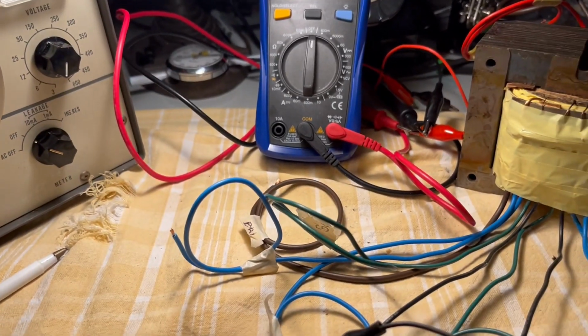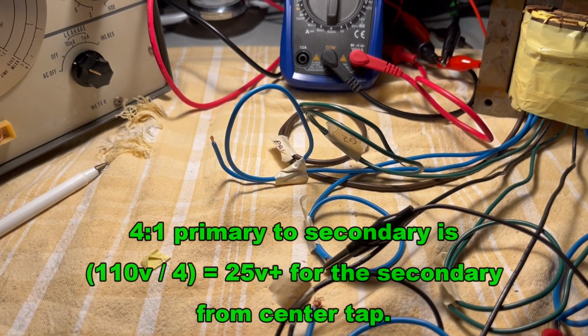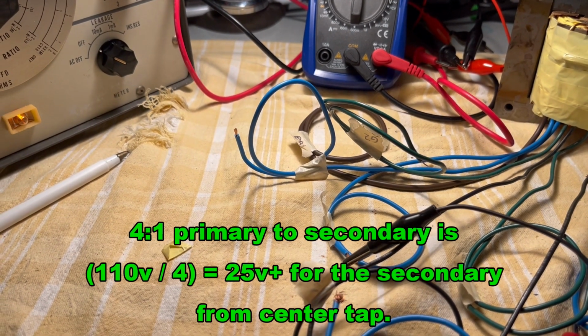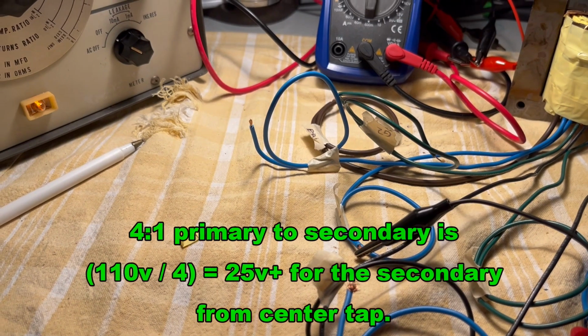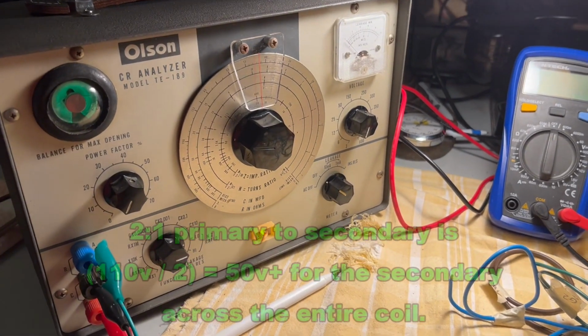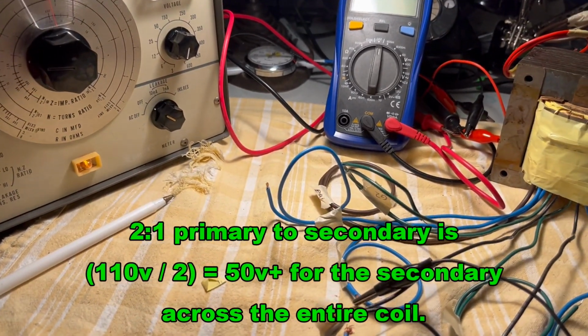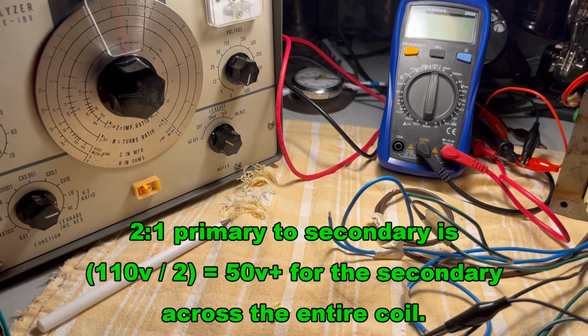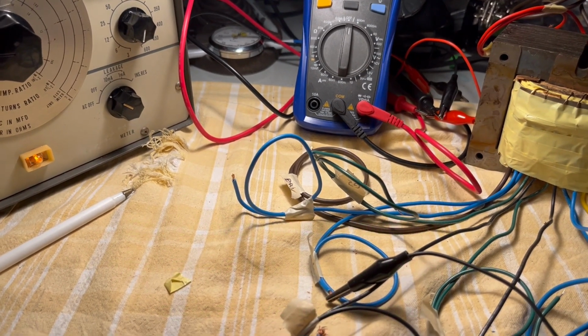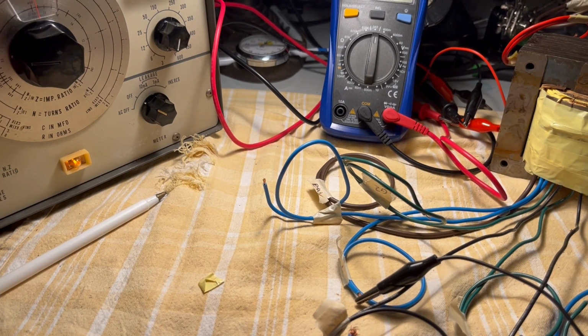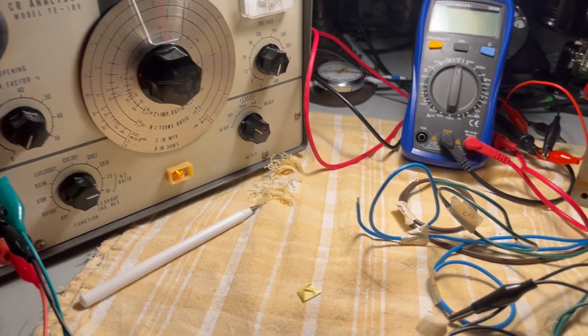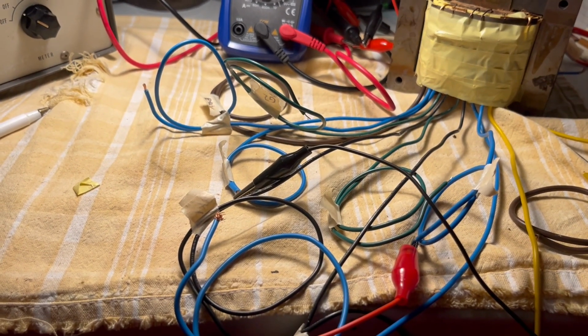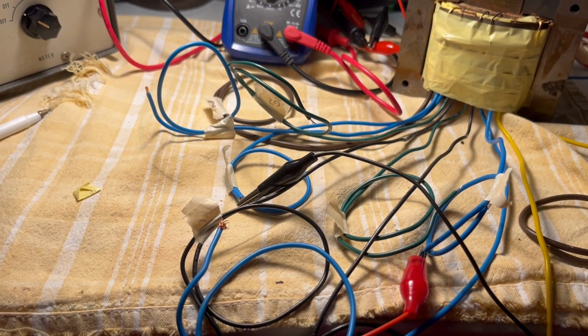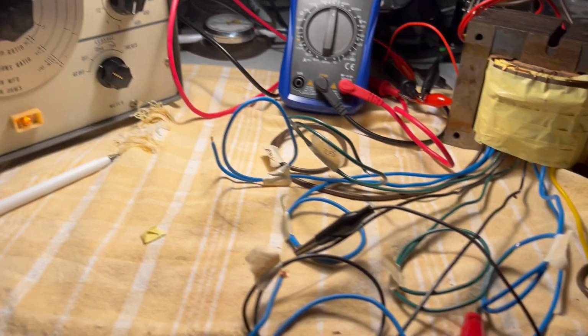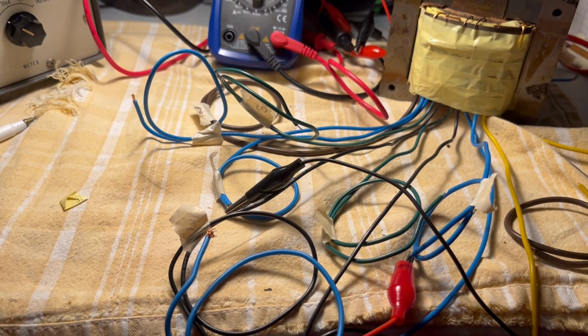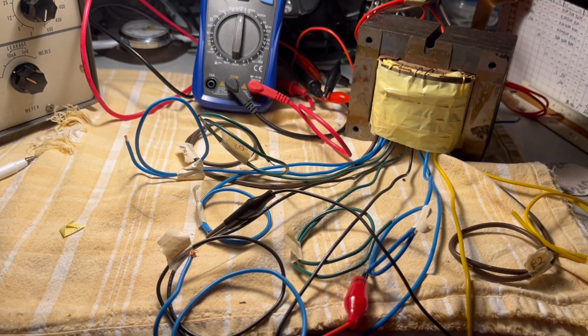So the first one, the ratio was 4-to-1 on the primary to the center tap on the secondary, and it was 2-to-1 this time, going end to end across that same coil. So the first time you can look at it and say, okay, well, we've got 110 to 120 volts, so it's half that. So yeah, it's enough to let you determine which end is which. And from this one test, I can tell which coil is which, and I can tell which is the positive side of the secondary and which is the positive side of the primary. And that's really all I'm going for here, is to just check to see that it looks like it's set up right to handle the voltages that it was designed to hold.